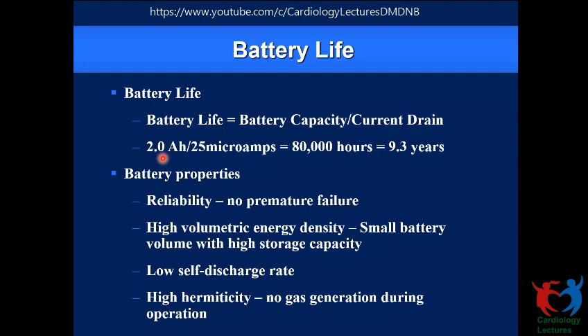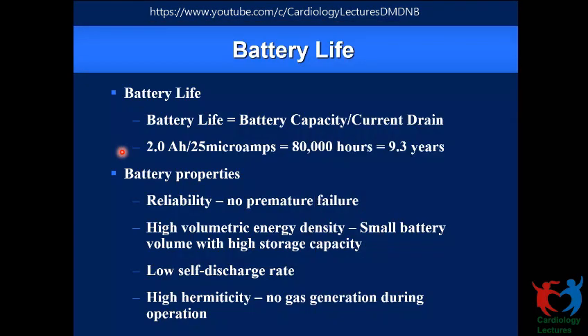So long we discussed the current outgo, and as a result the energy outgo for the pulse that we are delivering. But that's not the only current drain that we're talking about. In a pacing system, there is energy consumption when the pacemaker senses. There is a microprocessor that is running, and you need power to run that. Then there is a capacitor network to drive the output that also consumes some power. And the modern pacemakers are monitoring themselves and storing the electrograms, etc. That also consumes power.